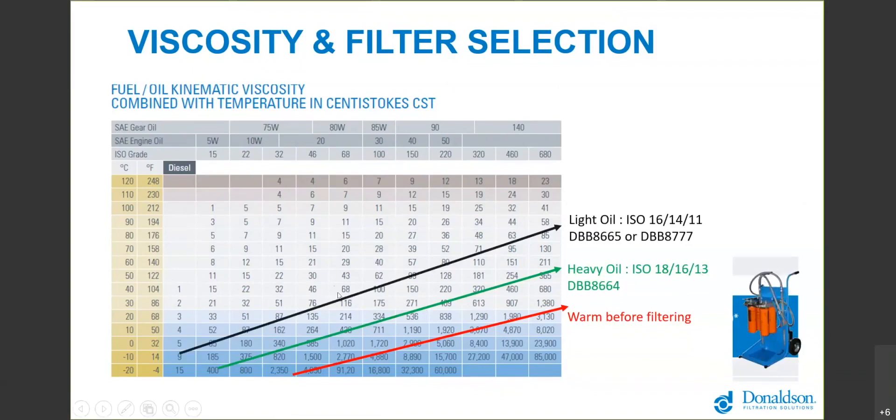Between 100 and 300 centistoke viscosity, we would recommend a light oil filter which would produce an ISO code of 16/14/11 downstream. There's two part numbers, this is our light oil filter and this is our winter fuel filter. Here's an example of our hydraulic cart. It's got a white suction strainer and then it goes in series filtration with particle filtration followed by water absorption.